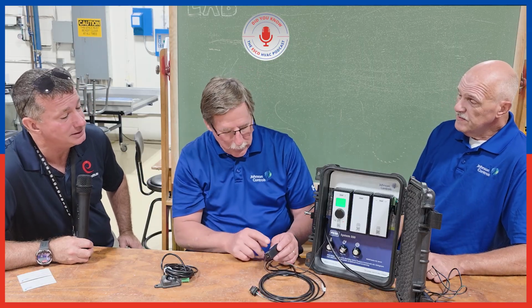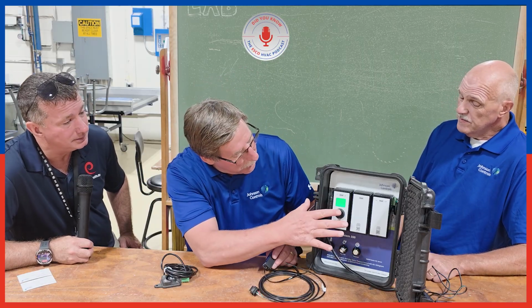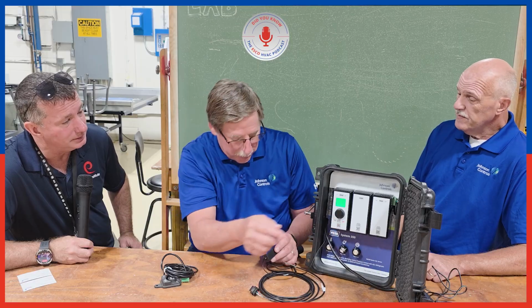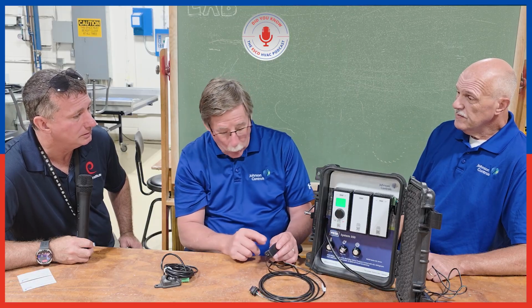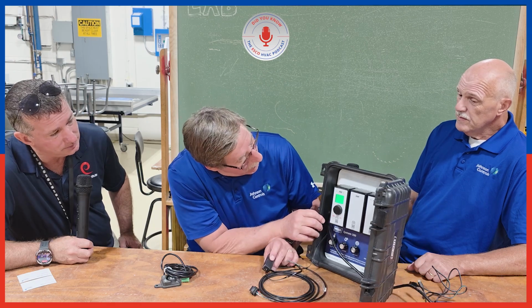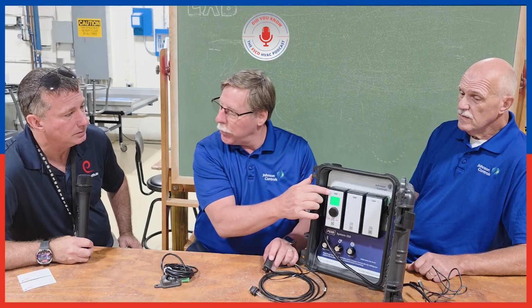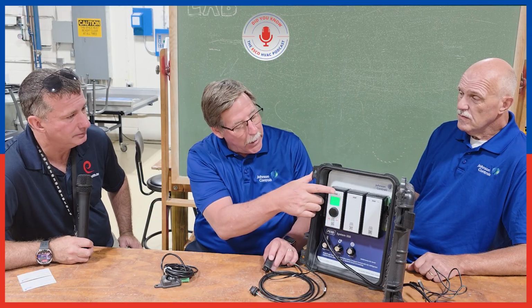Yeah, that's really nice. So now I'm at 10% and I'm warning because the light's on here. And then if I take it to 25%, which is above my trip point, you can see that I've now gone into secondary alarm mitigation. What does that mean? Well, I've turned my compressor off and I'm turning my evap fans on to get circulation, to dissipate the concentration of refrigerant to get it below that 20% LFL trip point.